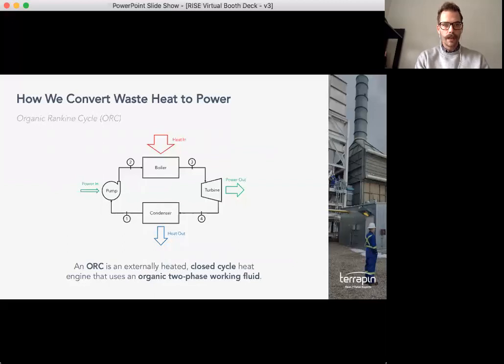As you can see here, we would integrate a heat exchanger into the stack that emits the waste heat and install a bypass damper. That waste heat is diverted into the ORC heat exchanger, which transfers the heat into the closed loop ORC working fluid, which is represented here with heat in.